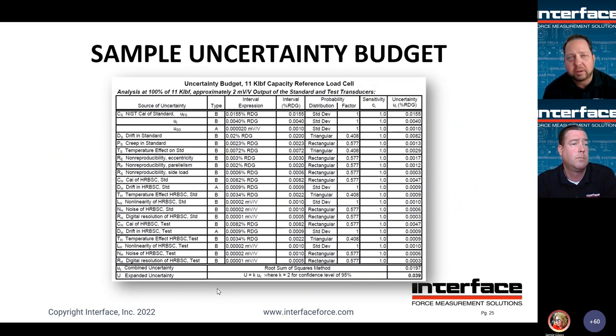This is an example of a calculated uncertainty budget for an 11K reference load cell. And we've got uncertainties that even include the NIST standard calibration that was done originally. So the NIST-based cal where the standard was calibrated, what is the error uncertainty contribution from that? Then you have, of course, the individual reading contribution, and then you start factoring in what type of distribution factors you want to have for each one. So there's standard deviations, triangular, rectangular. It's a function of how that's going to impact. And then there are factors from there, sensitivity, with the goal of arriving at a total uncertainty of reading.